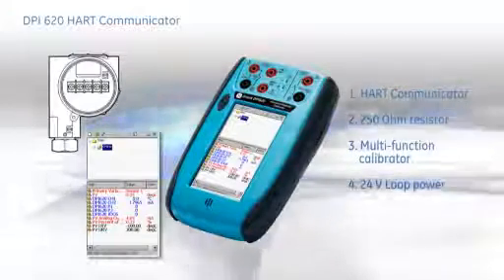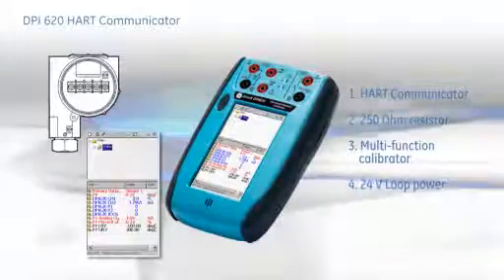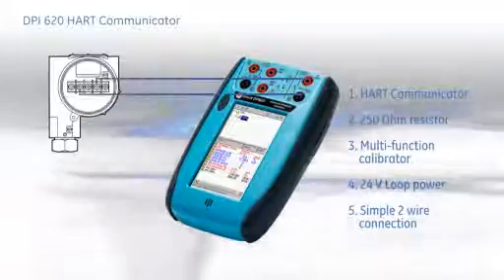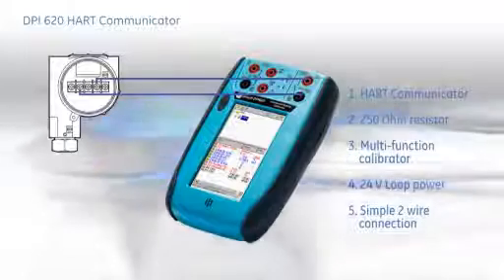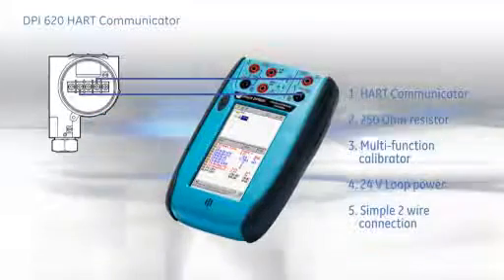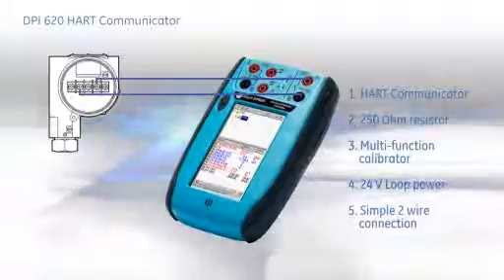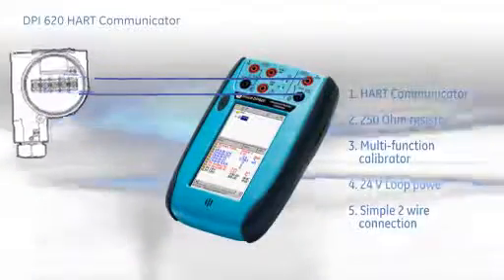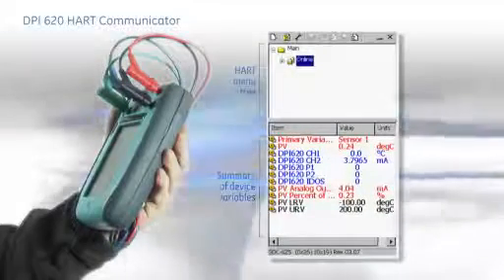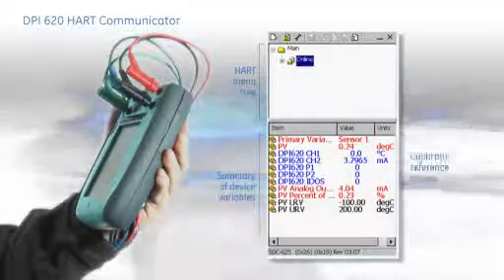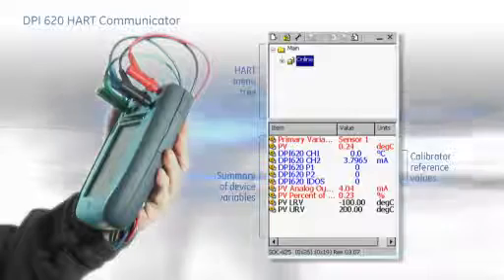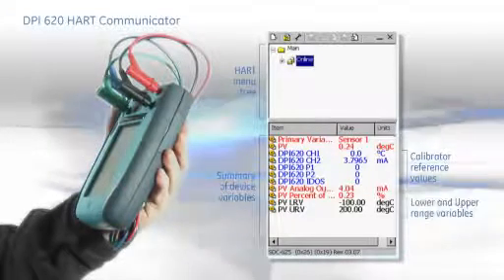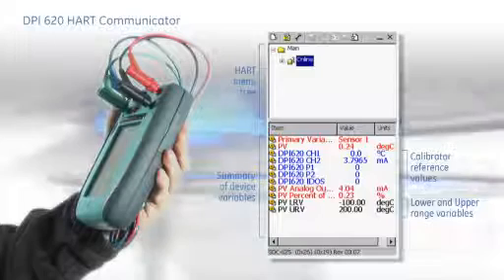Connecting to a HART device is simple. Just two wires. Select 24 volt loop power and a 250 ohm resistor as required. And the DPI-620 will then find the correct DD from its internal library. The initial summary screen shows the device variables in red, the actual reference values measured by the DPI-620 in blue, and the device upper and lower range settings in black.